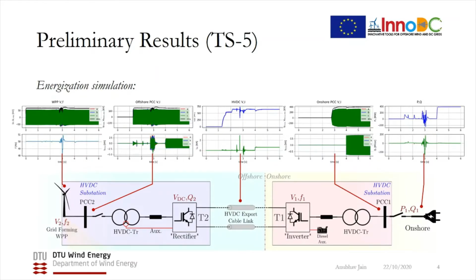After completing my courses and the literature review, I began simulation studies, starting with the overall energization sequence before focusing on details. This slide shows preliminary results of a complete energization simulation of an HVDC connected offshore wind power plant: islanded grid forming operation, offshore transformer and MMC cell energization, HVDC link voltage control by the offshore MMC, then onshore MMC controlling voltage and frequency at the onshore point of common connection, and finally onshore block loading as the last step.